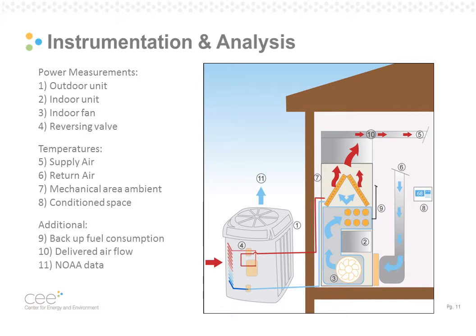We're doing 2 different types of analysis using the field data. The first is looking at the annual energy and cost savings from this system. So we're really taking a closer look at the reduction of delivered fuel use. And then we're also doing calculations of the performance for the air source heat pump and the furnace. So we're looking at the coefficient of performance for the system, and we're looking at this on a daily average and also per heating cycle.